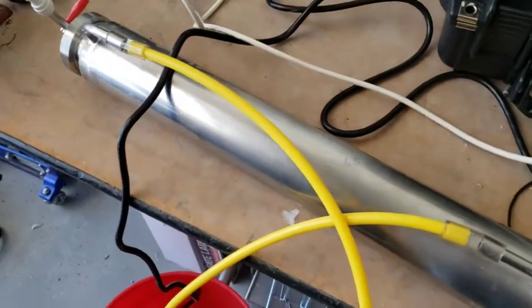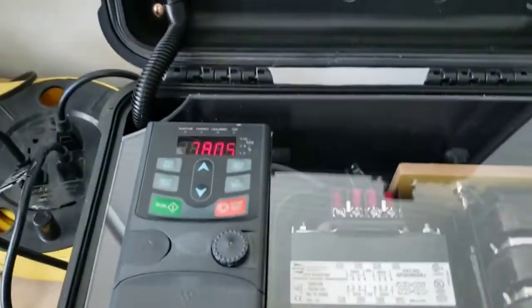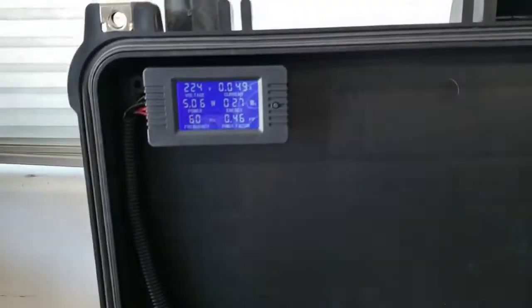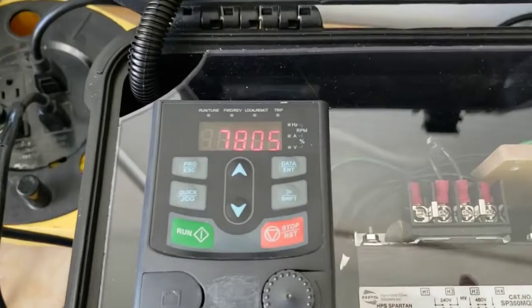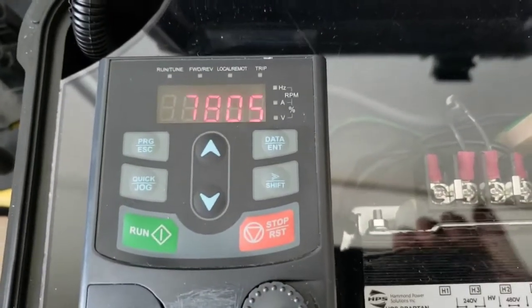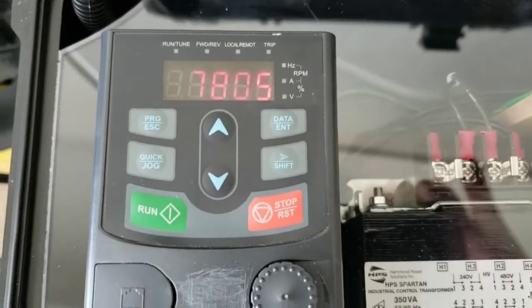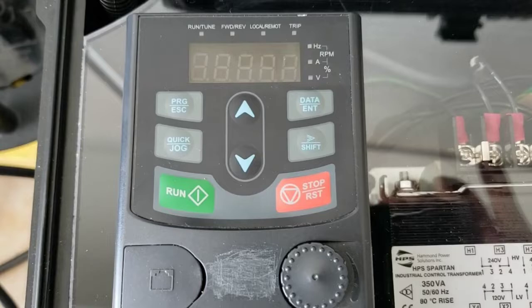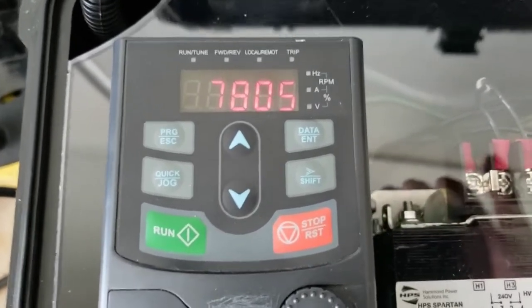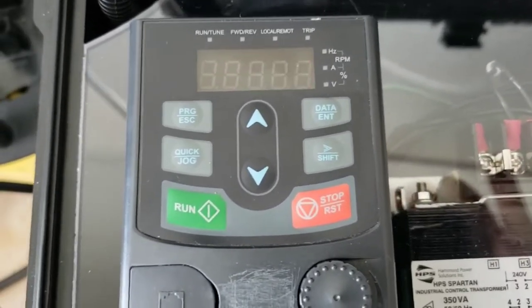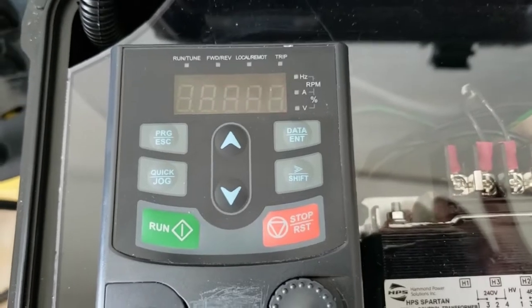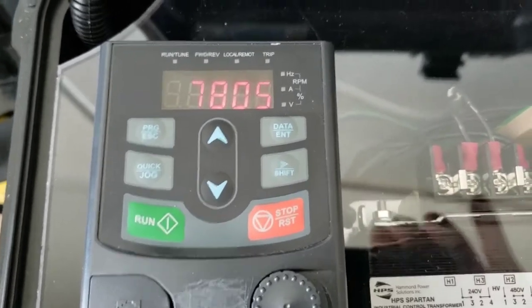But a lot of it comes down to just listening to the cell, listening for arcing, and then watching the values. There is no lamp that turns on that says failed. You just need to know what you're looking for. So that's why I'm doing this video, so you'll understand what values are okay. And again, if you're doing the auto-tune sweep, it'll generally do a really smooth sweep all the way up to 9500 hertz. If it doesn't, it gets hung up somewhere, and when you start hearing some arcing, you'll know that that cell is not good.